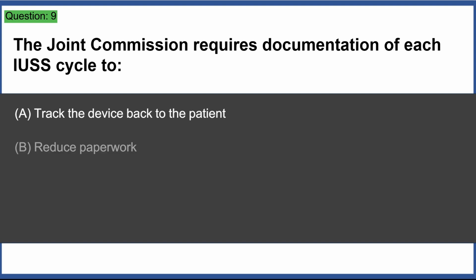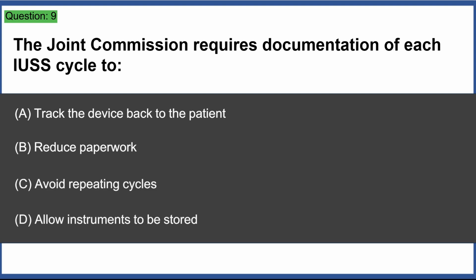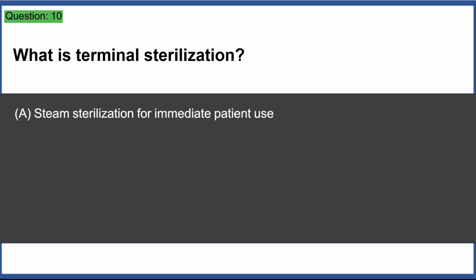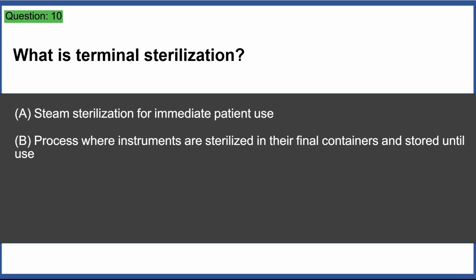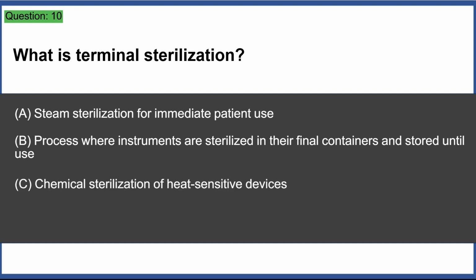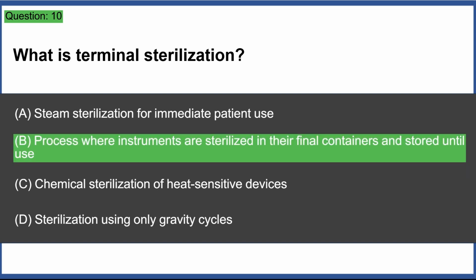The Joint Commission requires documentation of each IUSS cycle to A. Track the device back to the patient. B. Reduce paperwork. C. Avoid repeating cycles. D. Allow instruments to be stored. Answer: A. Track the device back to the patient. What is terminal sterilization? A. Steam sterilization for immediate patient use. B. Process where instruments are sterilized in their final containers and stored until use. C. Chemical sterilization of heat-sensitive devices. D. Sterilization using only gravity cycles. Answer: B. Process where instruments are sterilized in their final containers and stored until use.